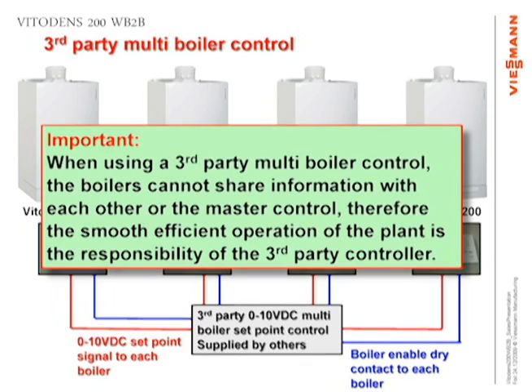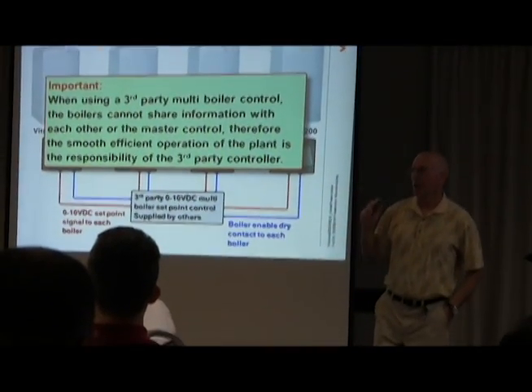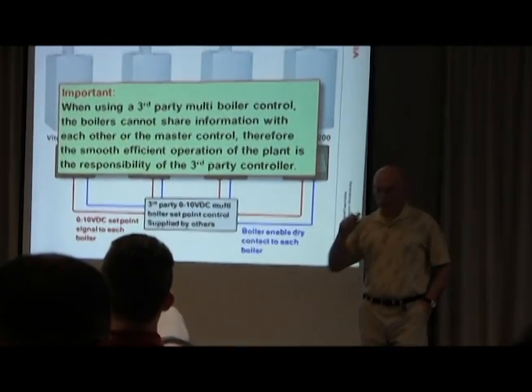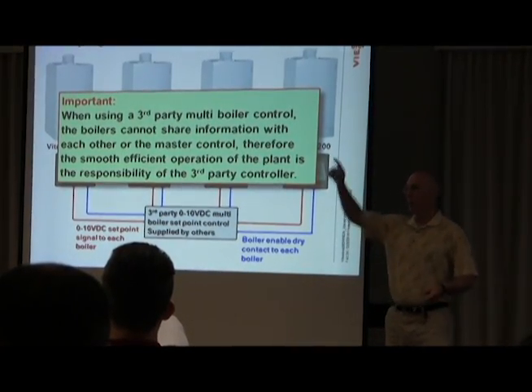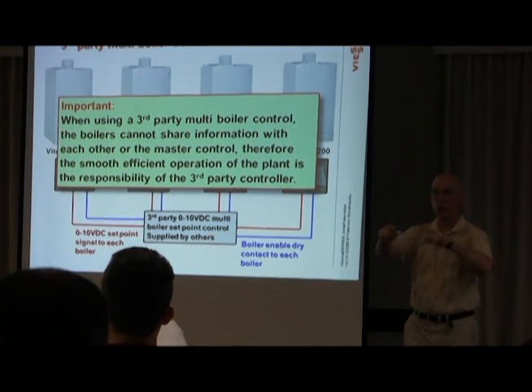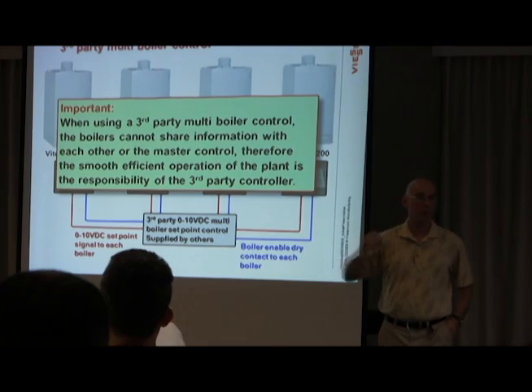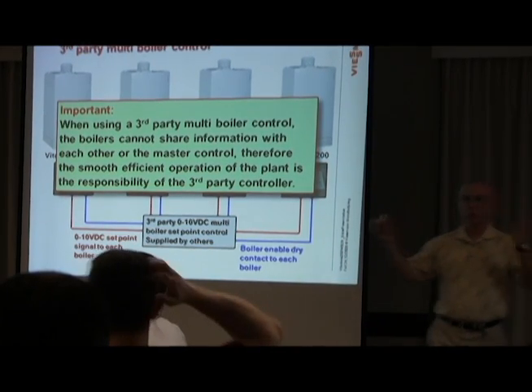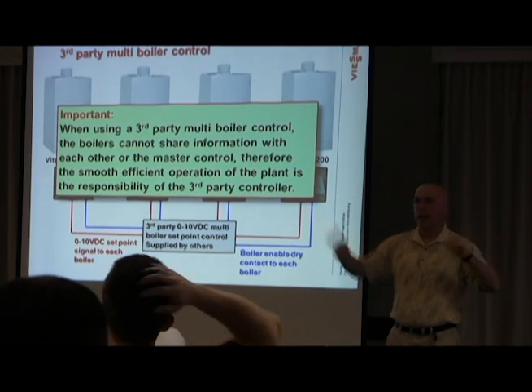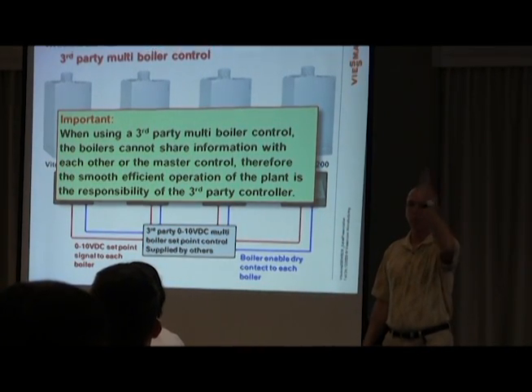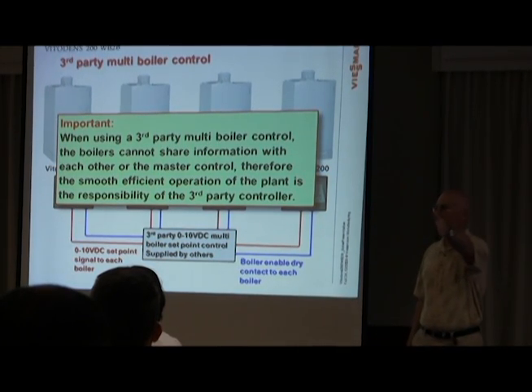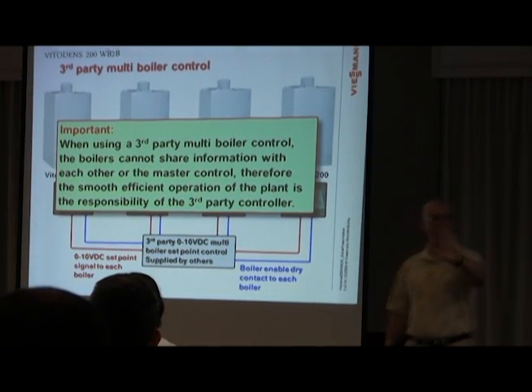This is important. If you use a third-party controller, please know now that the pieces don't talk to each other. It's a one-way street. If you use a Vitocontrol-S, there are advantages to that because the main control can talk to each individual boiler on its own. If you have a 4-boiler bank, and boiler number 2 goes out for some reason on a fault, you still have 3 boilers that can operate. It'll just tune that one out.